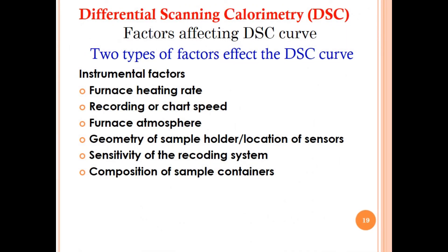Various factors affect the DSC curve, falling into two types. Instrumental factors include: furnace heating rate, recording or chart speed, furnace atmosphere, geometry of the sample holder, location of sensors, sensitivity of the recording system, and composition of sample containers.